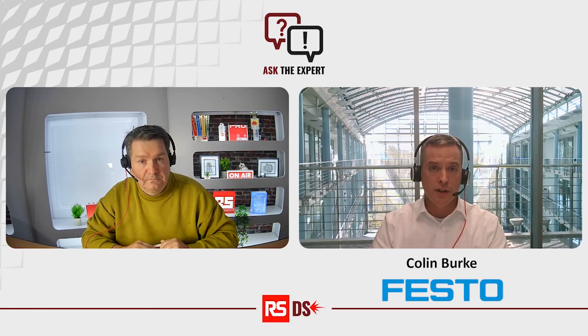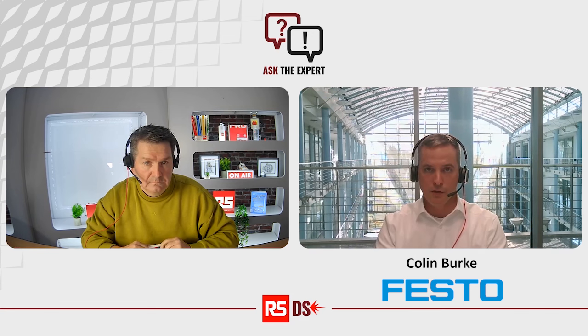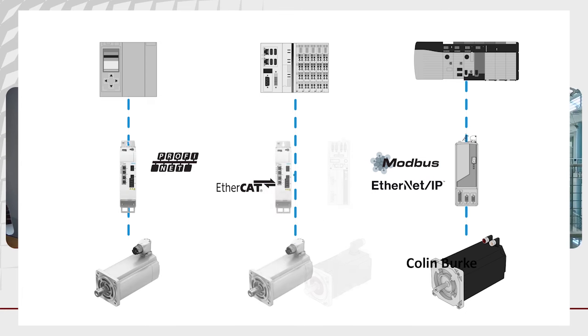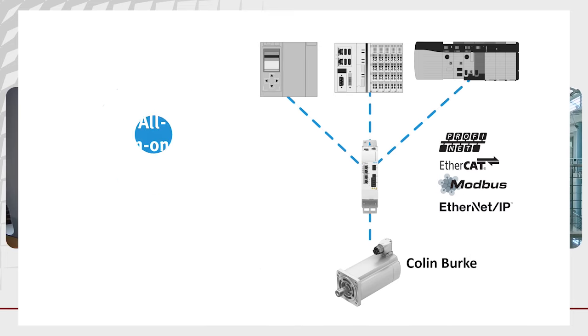The CMMT servo drive range is relatively new. We only brought it to market in 2018. I was mentioning earlier, we've got 10 part numbers which will cover from 150 watt 24 volt DC up to 3-phase 12 kilowatt. And they are multi-protocol. So they've got EtherNet/IP, EtherCAT, and Profinet. So with these 10 part numbers, you can have the whole range.